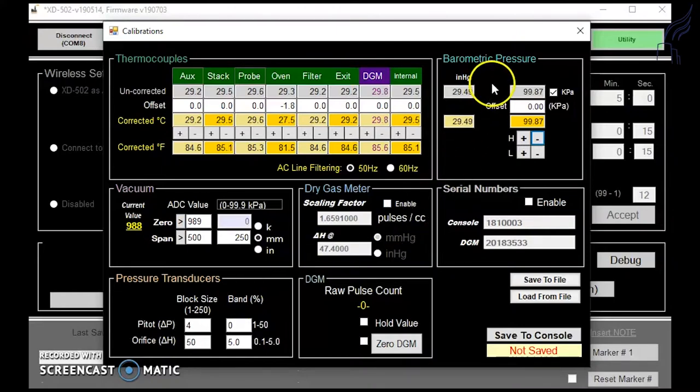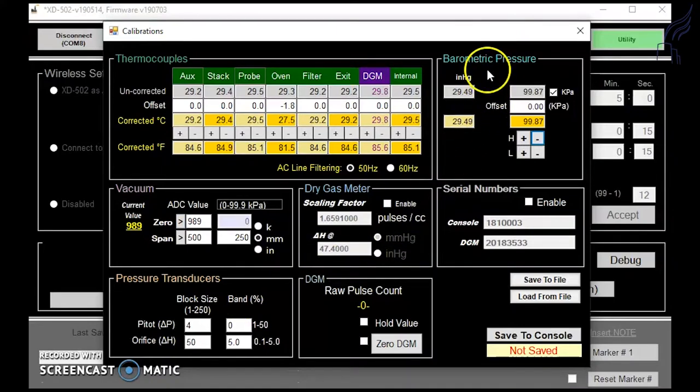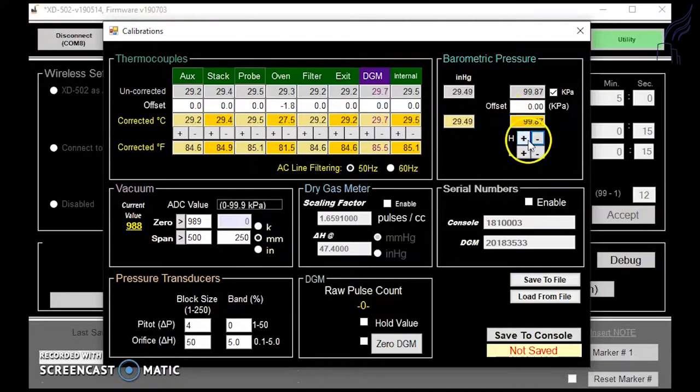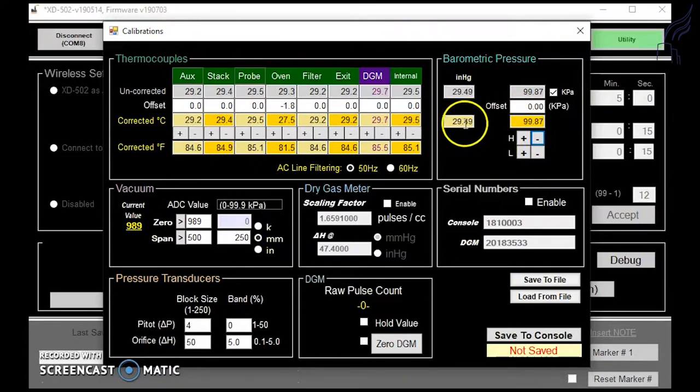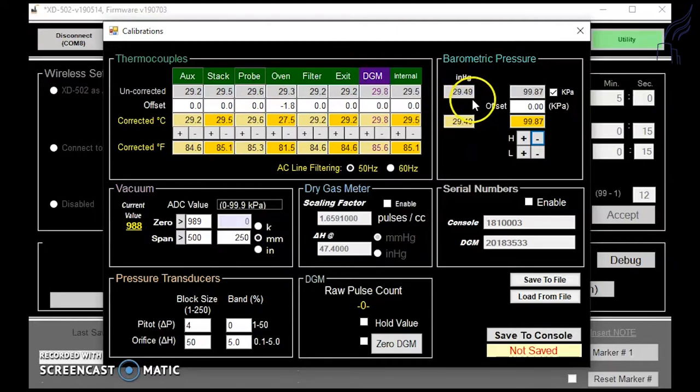For barometric pressure, we can use a reference barometer to add the correct offset as well. We'll do this so that our console reading matches what the reference barometer reads.